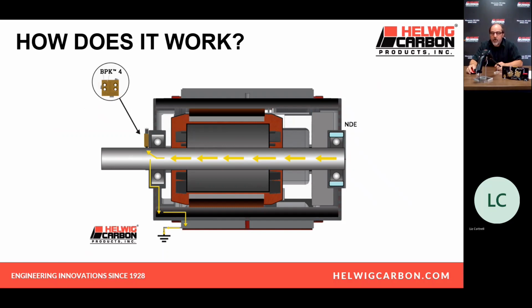As you can see here, we're going to mount our kit right up on the shaft. It's going to physically contact the shaft. That's going to take the charges that you see in the yellow arrows that build on the shaft, the common mode voltage, and it's going to redirect that voltage through our brush to ground. We do not allow discharges through the bearing because voltage, like anything else, is going to find a path of least resistance. And we're talking micro ohms of resistance from our brush to ground.